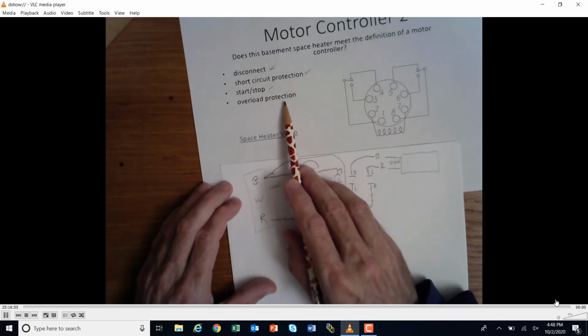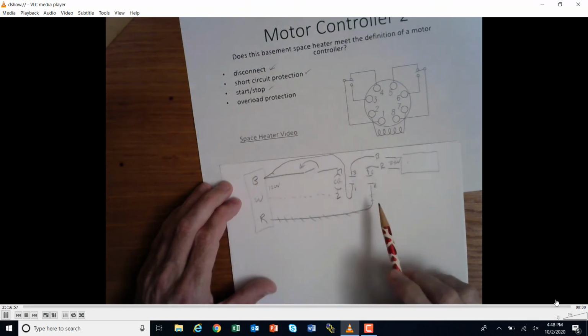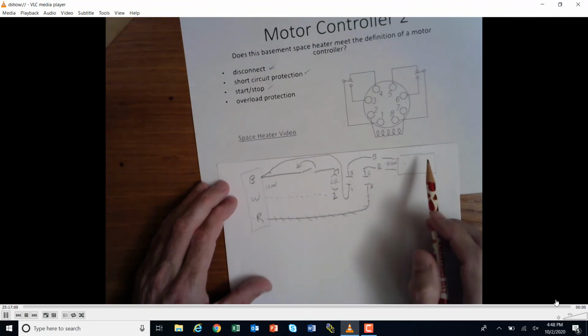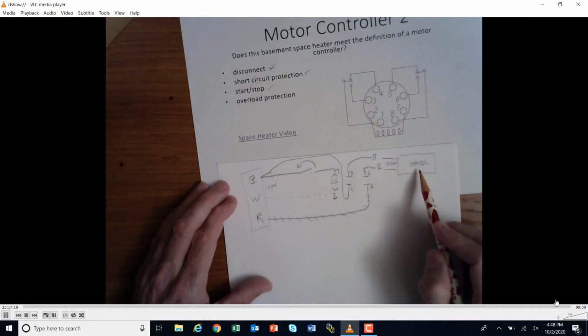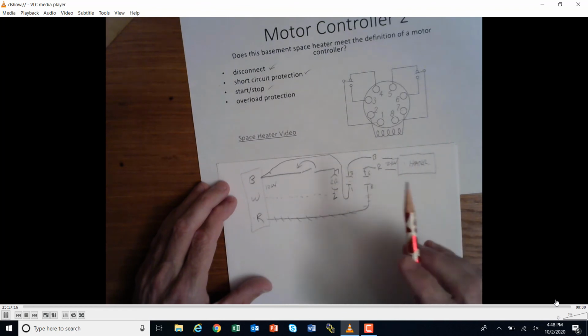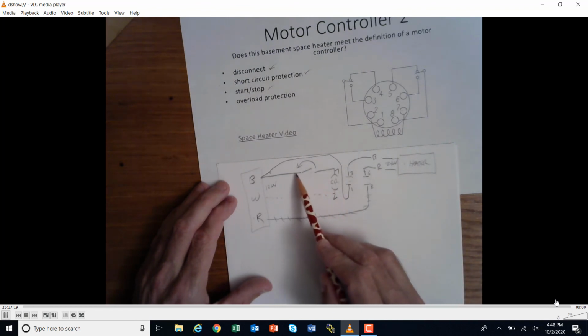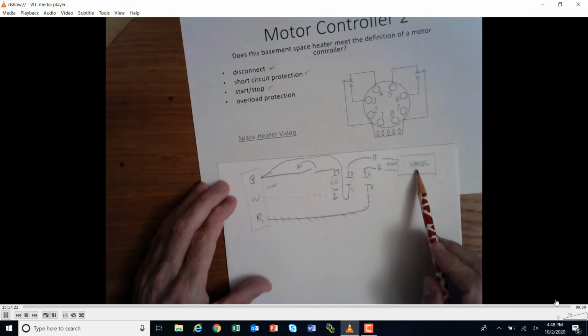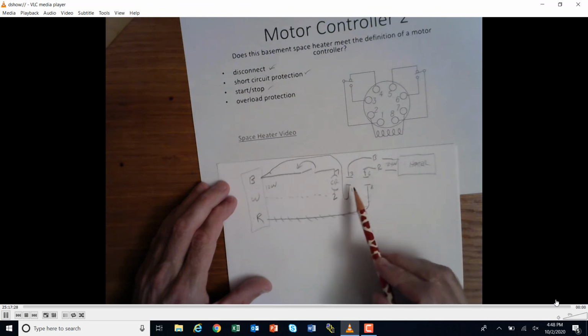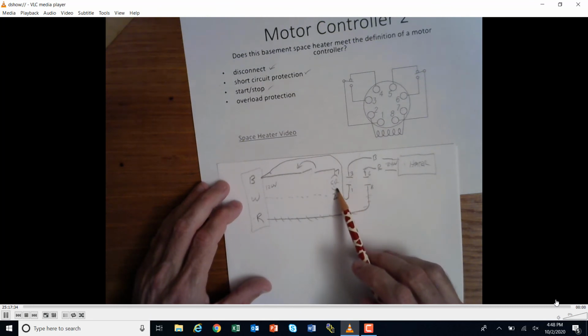Did I have overload protection? Not in the sense we have for motor controls, but the heater does have an internal overload. So if it got too hot, it has an overload that would trip and shut it off. The control relay would stay on if the switch was closed the whole time - the heater would just stop working until it cooled down, then start right back up since those contacts would remain closed. So it didn't have low voltage protection to drop out the control relay, since there was no memory here, just this maintained timer switch.